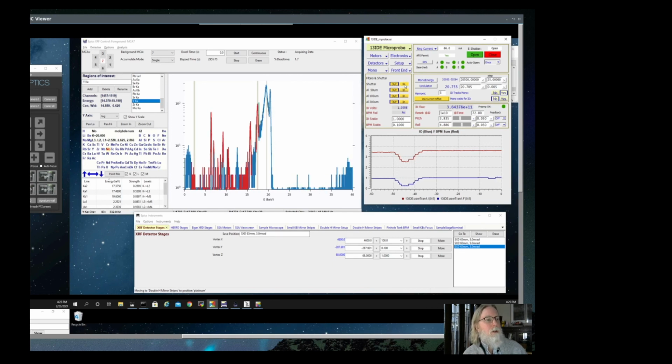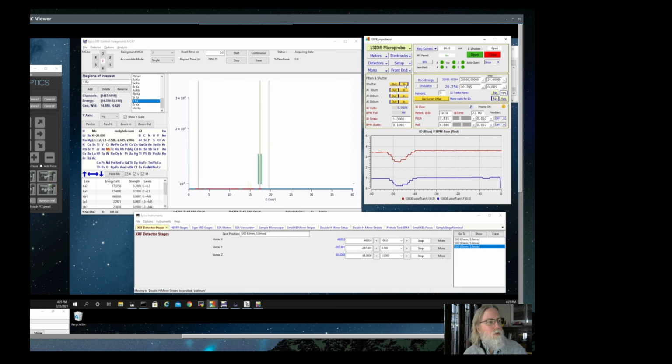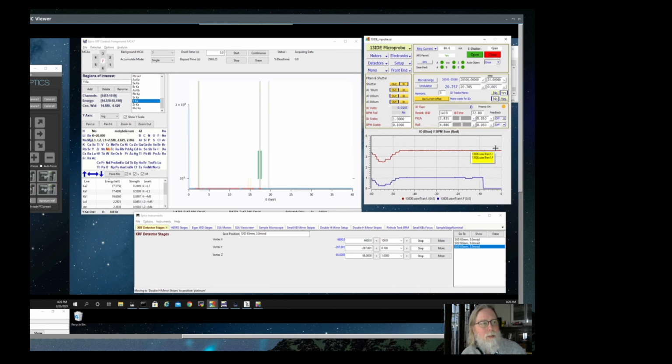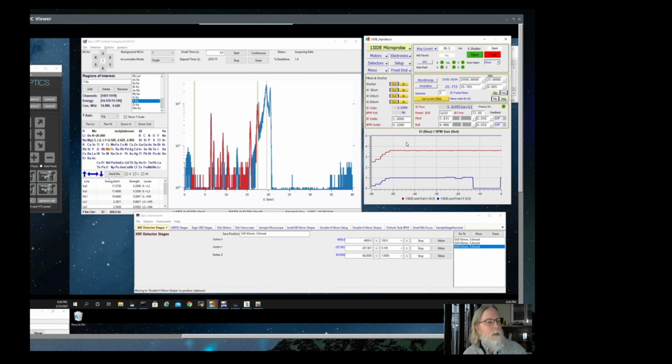And we also have a shutter, just a piece of lead on that filter that we can drop into the beam. And when I do that, the X-ray fluorescence spectra goes away. That intensity goes to 0, but the red line, the intensity upstream of the station, stays on. I open the shutter and the X-rays come back and illuminate your sample. So that's a good way to prevent the X-rays from hitting your sample or measuring dark currents and so on. We'll use that shutter for most of the time when we mean to turn the beam off, but not go in the station. So that's the overview of the data acquisition and control computers.